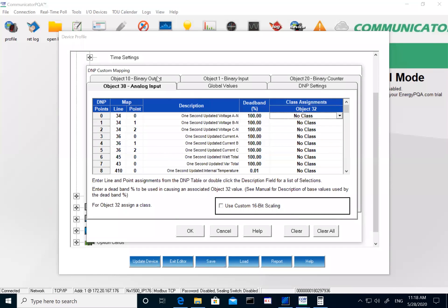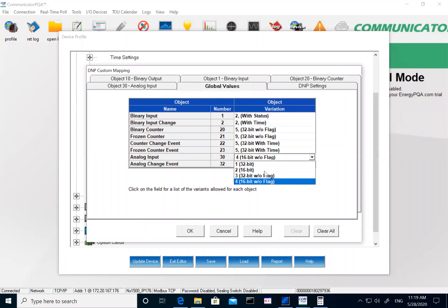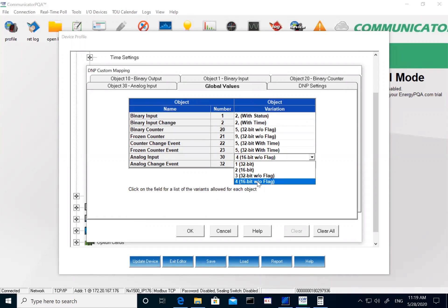Since the Nexus meters use 32-bit as a default, we have run into some customers who use older RTUs, SCADA systems, or PLCs that only support 16-bit scaling. You can set this up on the meter. Under Global Values, you can define the variation — if your RTU only supports 16-bit values, you can change the dead band variation to 16-bit. This depends on your system or the software you're using to pull the meter; we just have the ability to change it on the meter side.